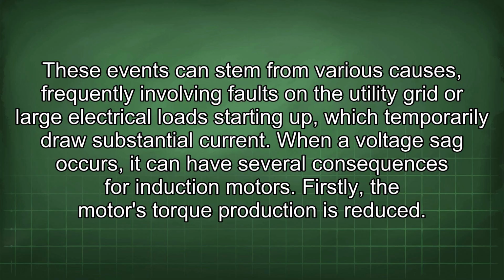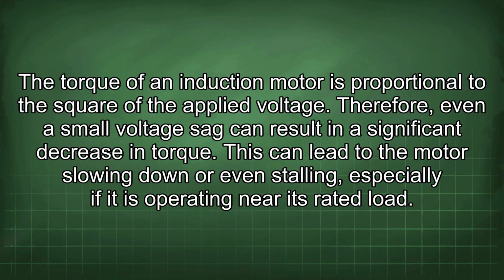When a voltage sag occurs, it can have several consequences for induction motors. Firstly, the motor's torque production is reduced. The torque of an induction motor is proportional to the square of the applied voltage. Therefore, even a small voltage sag can result in a significant decrease in torque. This can lead to the motor slowing down or even stalling, especially if it is operating near its rated load.